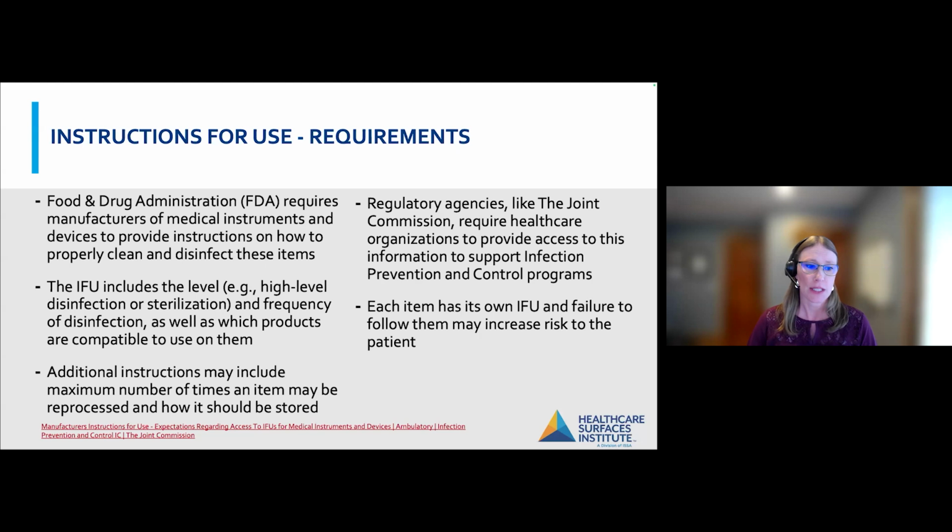Additionally, there's some instrumentation that might require a certain number of re-sterilization or re-disinfection processes before the item needs to be thrown away and replaced. A couple of examples of this that we commonly see in hospitals: in our sleep labs, we have masks that can either be disposable or reusable, but the reusable ones have a maximum of 15 to 20 uses. That means that the product can be disinfected 15 to 20 times, depending on the specific product that you have, and then it has to be discarded.